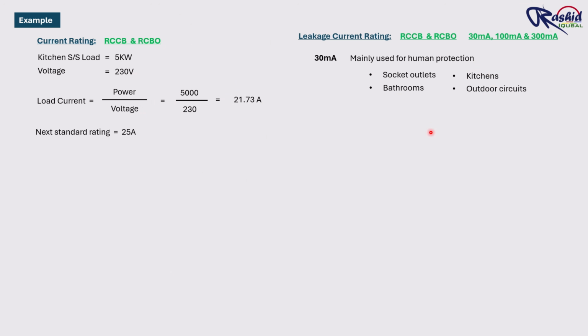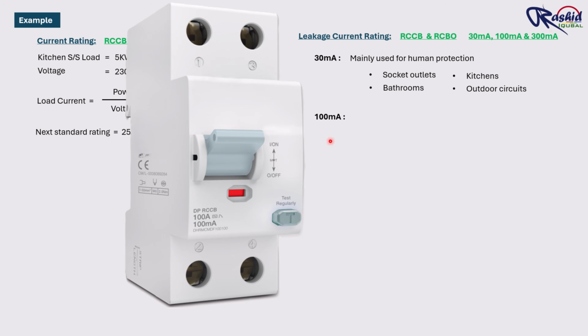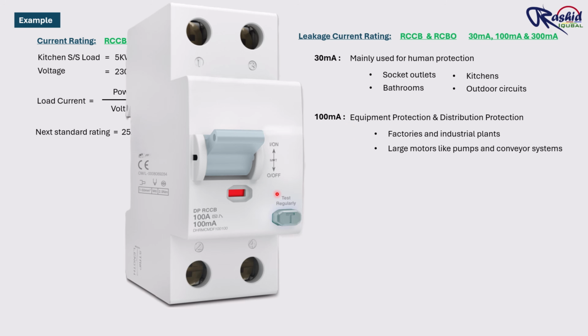Now you may have another question. If 30 mA provides human protection, then why do we also have 100 mA and 300 mA RCCB or RCBO? Why don't we use 30 mA everywhere? So let's understand. A 100 mA RCCB is mainly used for equipment protection and distribution circuits. In large installations, many electrical equipment and long cable runs can produce a small leakage current during normal operation. There is always a leakage current, but it is normal.